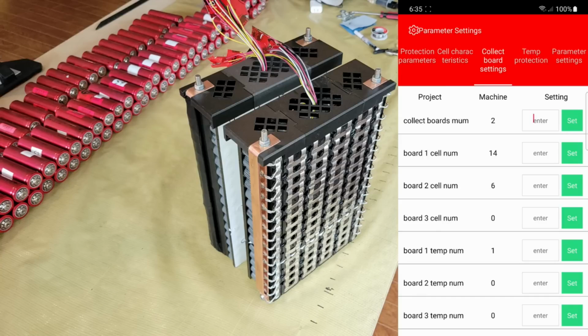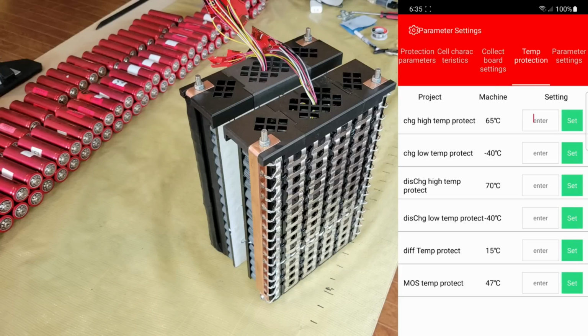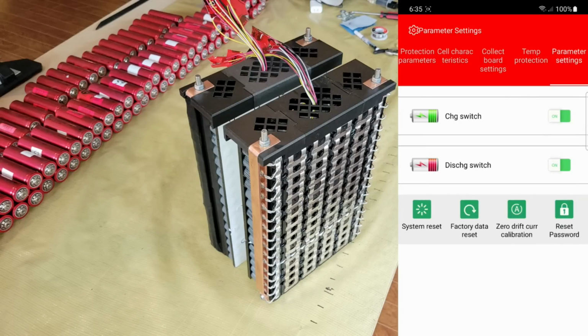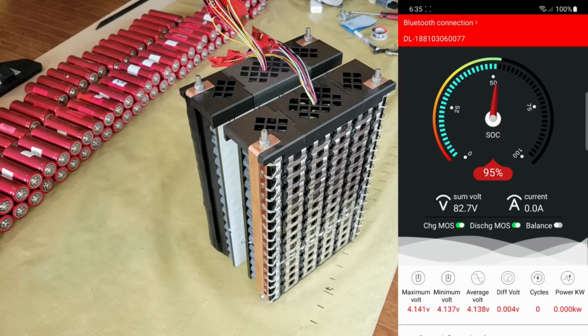The next section covers information about how many strings and temperature sensors you're using. The section after that covers the temperature protection settings. And the last section allows you to enable or disable the charge and discharge switches manually, perform a factory reset, or change your password.